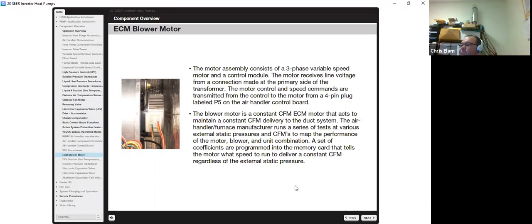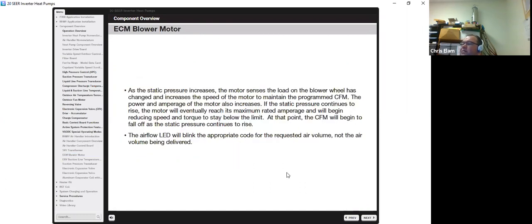The air handler and furnace manufacturer runs a series of tests at various external static pressures and CFMs to map out the performance of the motor, blower, and unit combination. A set of coefficients are pre-programmed into the memory module that tell the motor at what speed to run to deliver its constant CFM regardless of the static pressure. As the static pressure increases, the motor senses the load on the blower wheel has changed and will increase the speed of the motor to maintain the programmed CFM. The power and amperage of the motor will also increase.